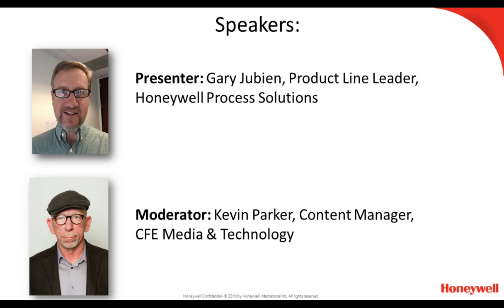Good. One of our listeners asks, is there value in doing an on-off test to estimate the benefit of the APC? Yeah, certainly. Let me answer that. I know this is often advanced as one of the proof tests of APC. I'll say a couple things on that. One is that if that's done after the APC is commissioned, it often shortchanges the value of APC itself. And the reason for that is, in doing an APC project, you really probe into the process. You figure out what should we be manipulating, what should we be controlling. Maybe, as one of the other listeners mentioned, there is a regulatory control problem that would stop us from implementing APC, and we'll get that addressed, right?